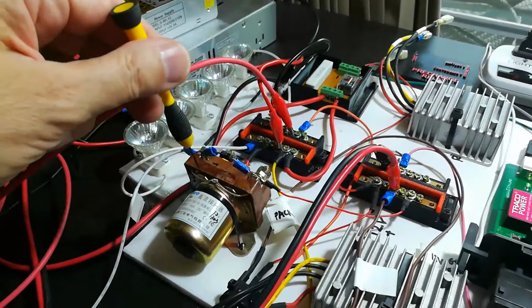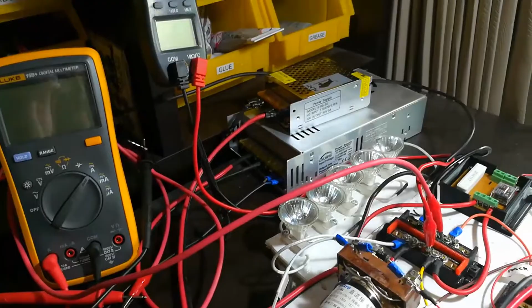With full power flowing through, I've got these halogen bulbs simulating the load of a motor. Right now these are 20 watts each, so we've got 100 watts worth of power consumption. The motorbike's got a 3000 watt motor, so that's very, very small, but at least it'll let me check the functionality of the precharge relay and the contactor, and make sure the power and current is coming through as we'd expect.